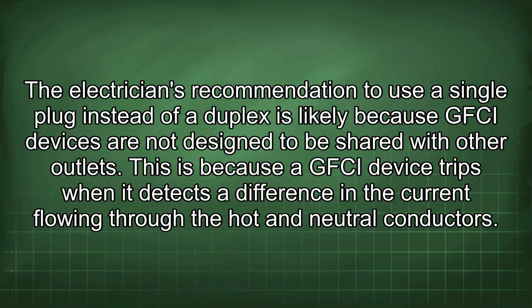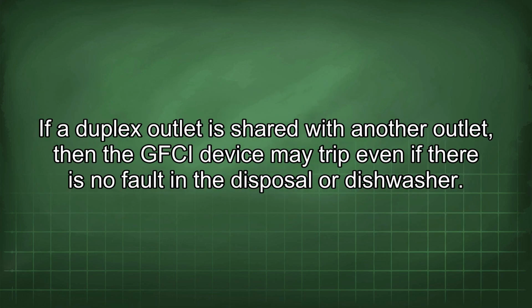The electrician's recommendation to use a single plug instead of a duplex is likely because GFCI devices are not designed to be shared with other outlets. This is because the GFCI device trips when it detects a difference in the current flowing through the hot and neutral conductors. If a duplex outlet is shared with another outlet, then the GFCI device may trip even if there is no fault in the disposal or dishwasher.